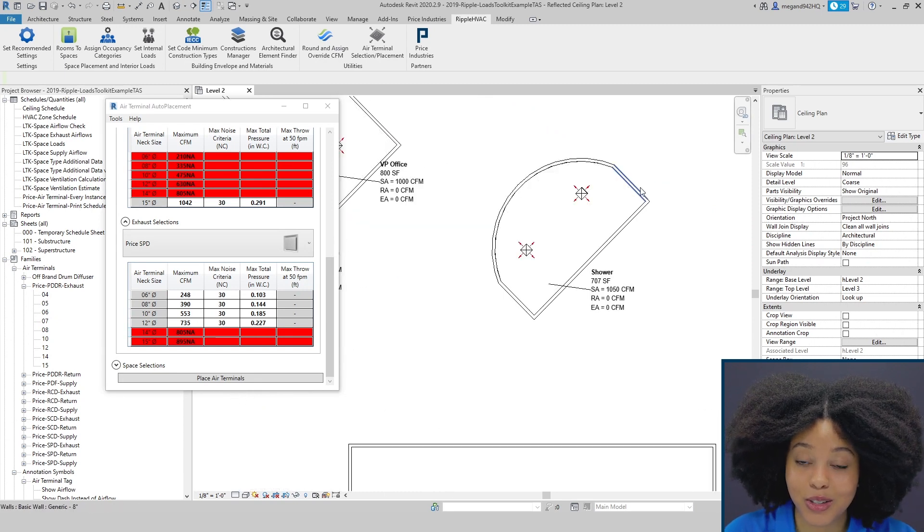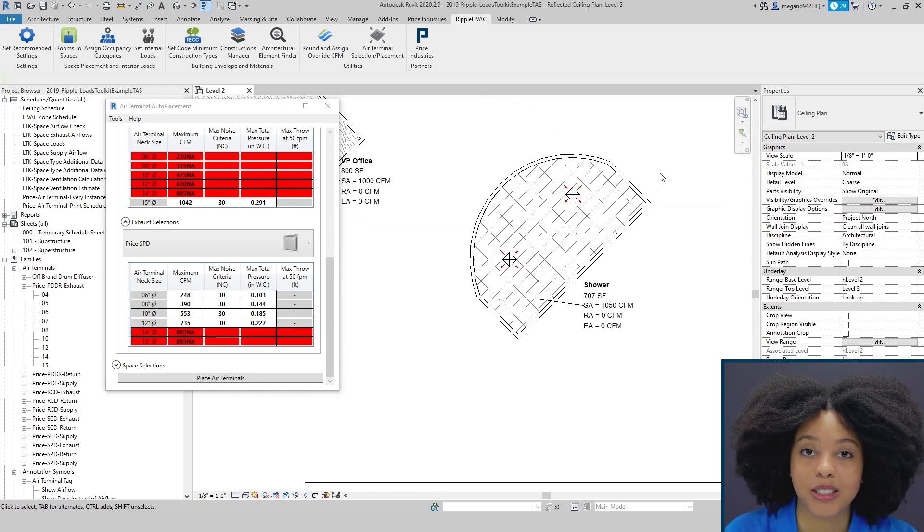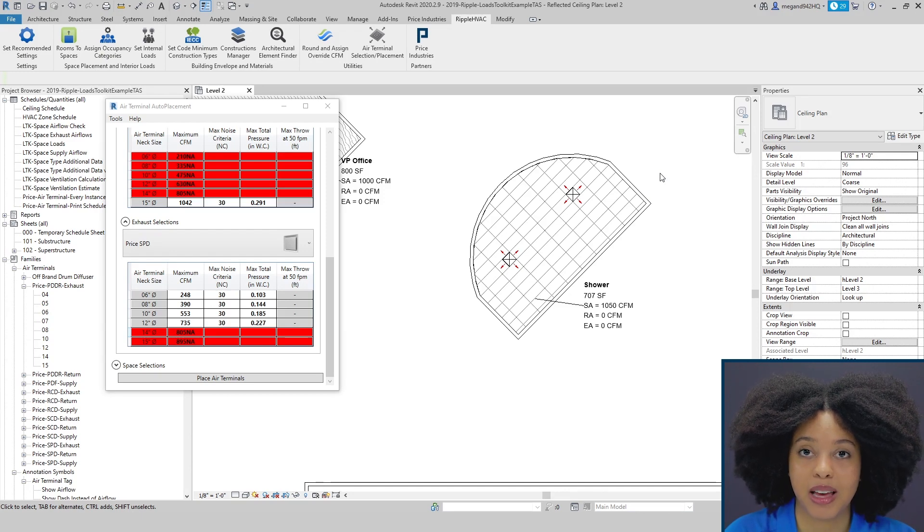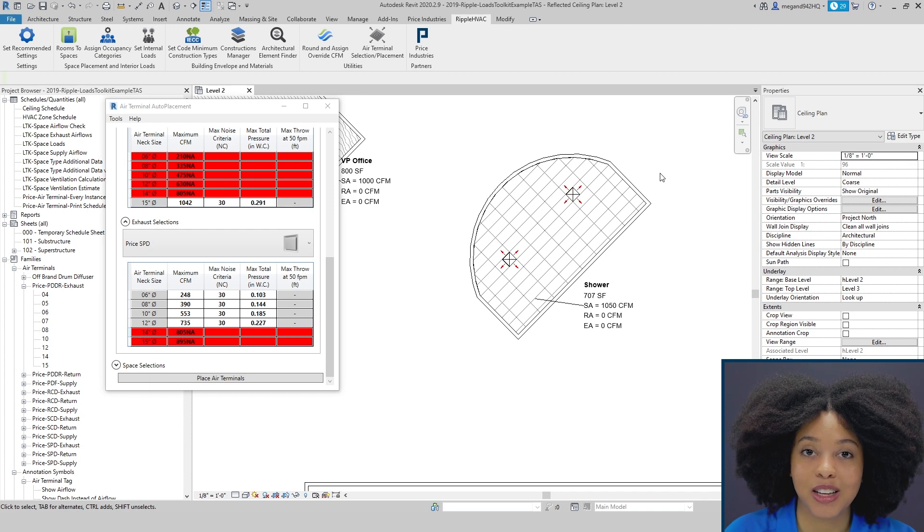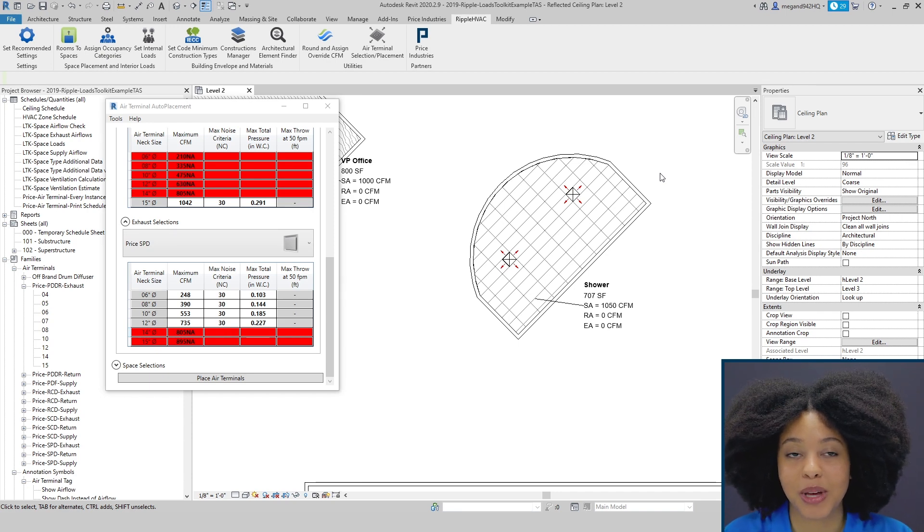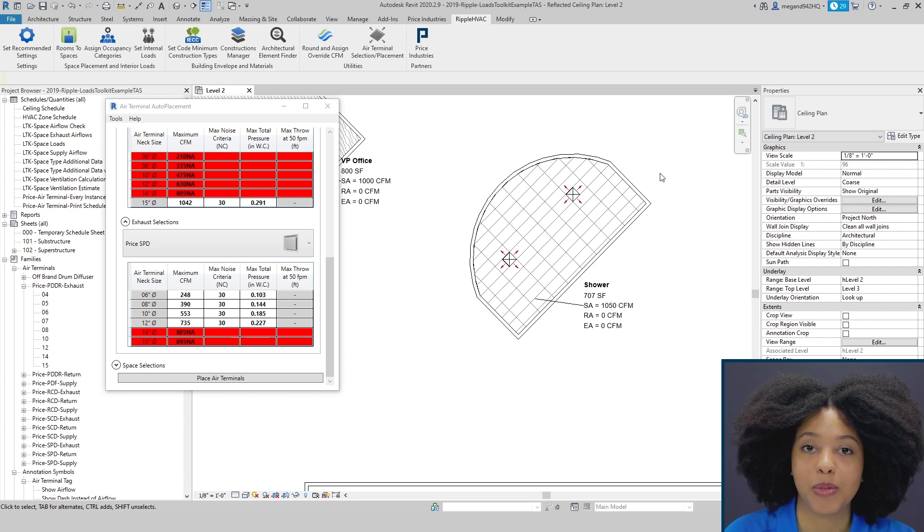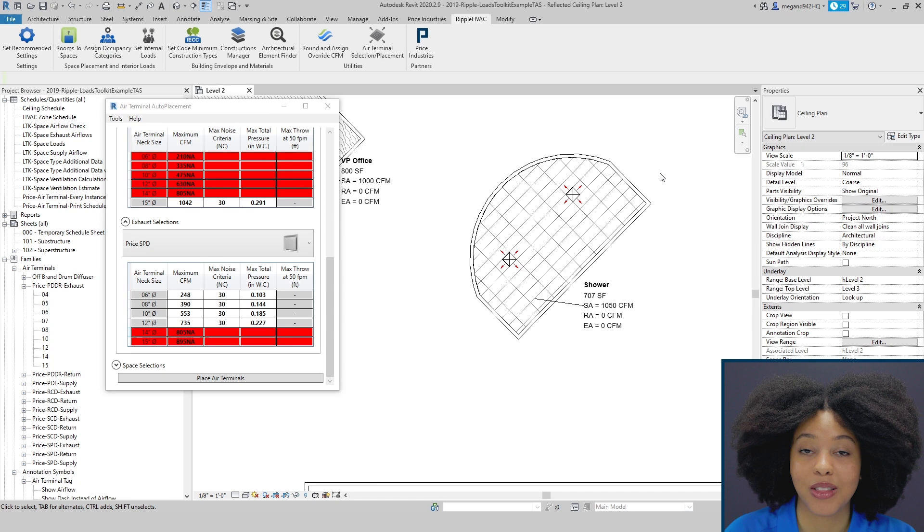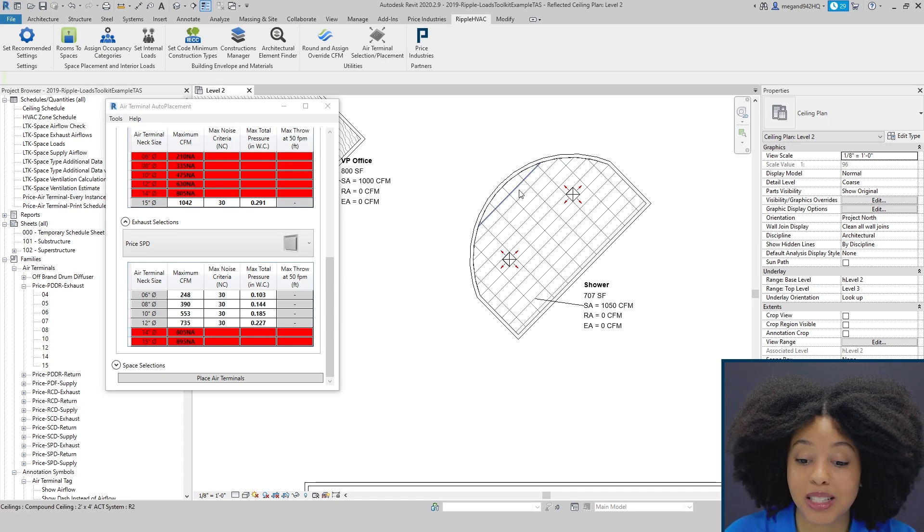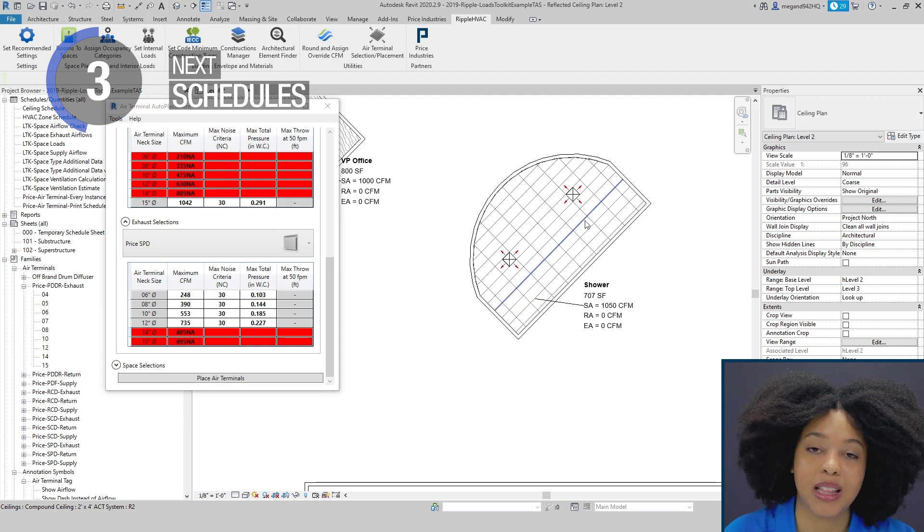It's also able to do curved applications. The tool works by taking complex shapes and simplifying them down into more basic rectangles. With that being said, the tool is designed to handle standard spaces. Your classrooms, your office spaces, it's designed to be able to automatically place the 80% of your projects so you can focus on that 20% and that's where your big time savings will come. Here a simple curve it is able to place your diffuser but as you get into more complex curves and shapes then it's best to manually place the diffusers out.